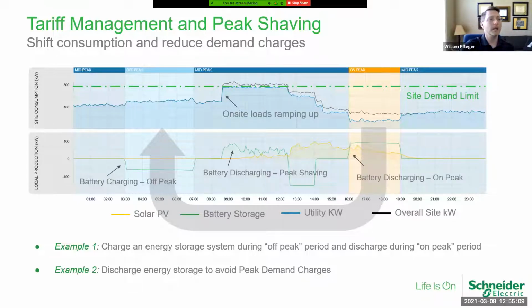What you can see here is that this site has a time of use tariff with low, middle, and high cost of energy periods. In addition, this site has to pay demand charges, with a threshold of 800 kilowatts. The system knows that if the load ever exceeds 800 kilowatts, this customer will be given additional charges, which can represent up to 50% or more of a particular utility bill, and may also have extending consequences for the rest of the year, as this site does.